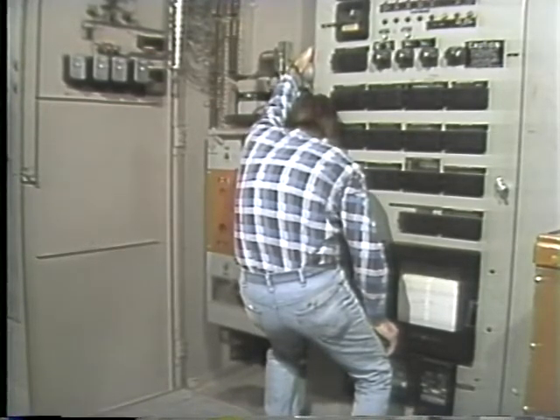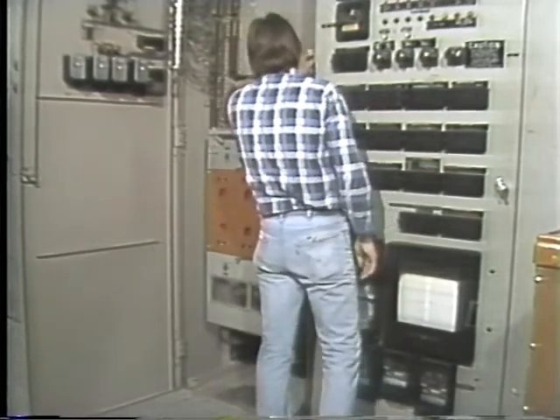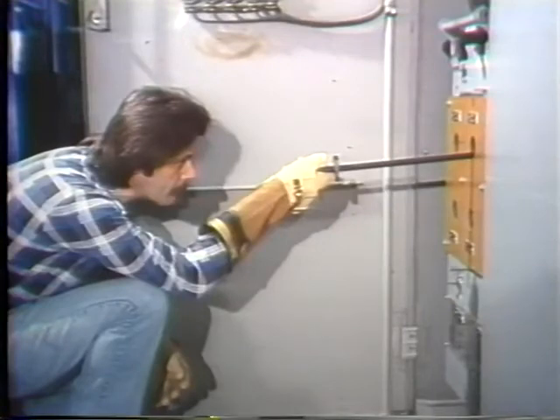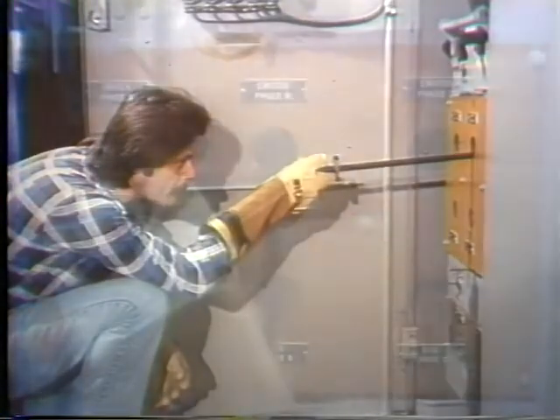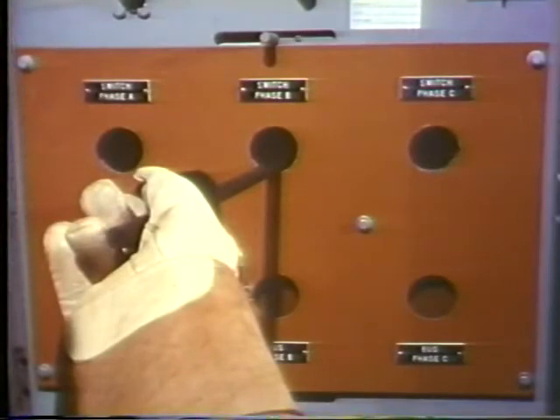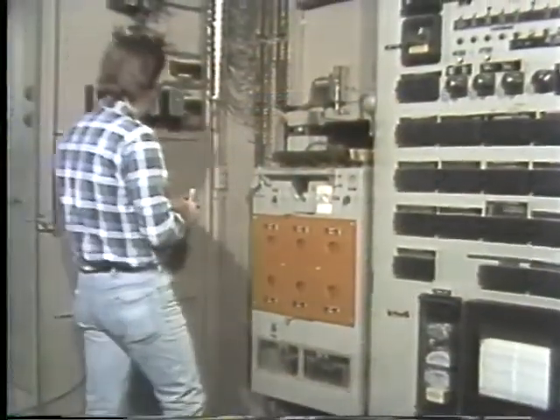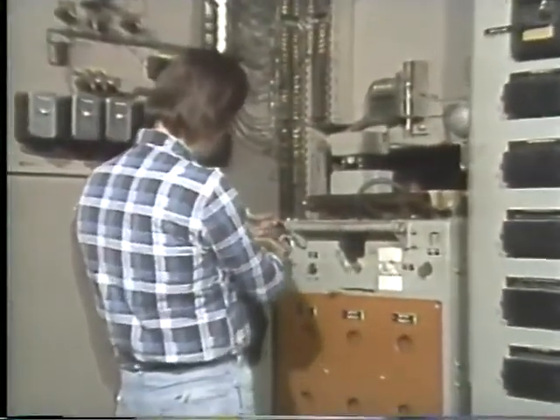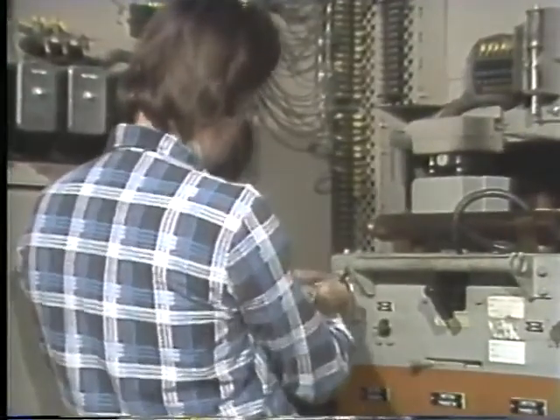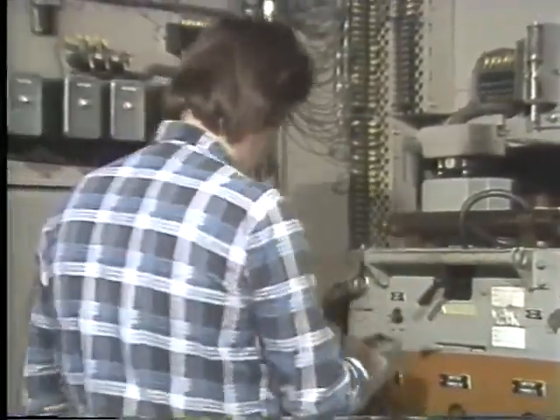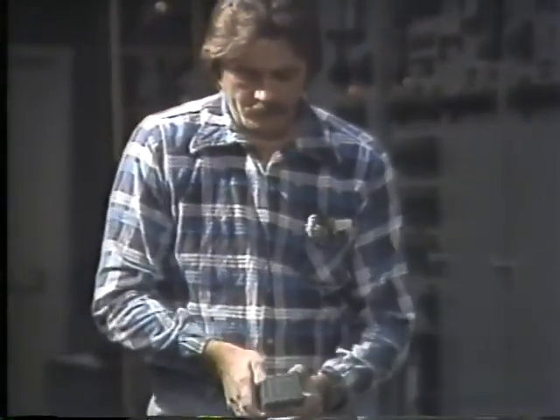Now the unit's fully racked into position, but the ground isn't closed yet. Before closing the ground, he tests all 3 line terminals for voltage. If the line was energized, grounding it could be an explosive experience. For extra safety, the switch that operates the device is mounted on a 50-foot cord. After it's connected, the electrician places the selector knob in the line ground position and steps back. Now the line is safely grounded.